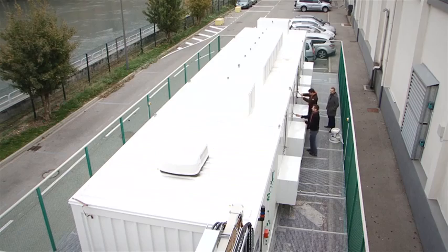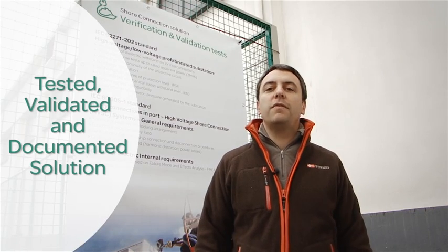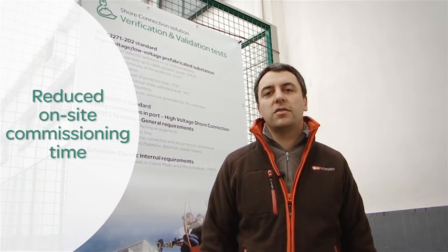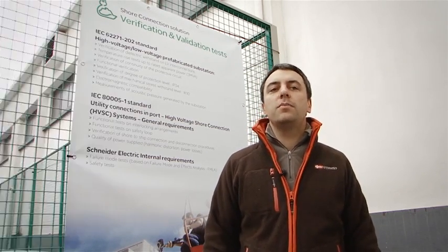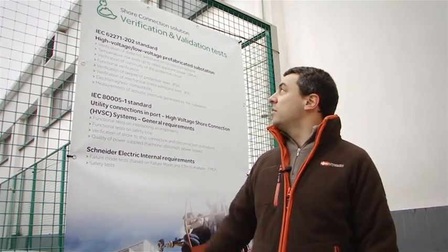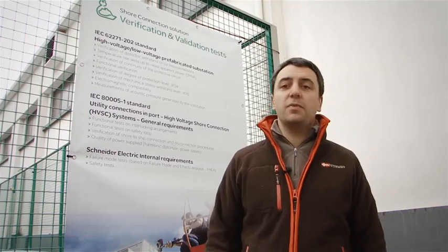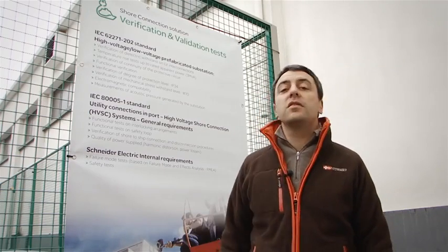An exhaustive test plan has been set up in order to test, validate and document our solution. The objective is also to reduce the time spent for commissioning on site. Verification of the design and performances has been made according to the standard IEC 62271-202 for HV substations. Among others, the tests performed were dielectric test, temperature rise test, verification of degree of protection, or verification of mechanical stress withstand.